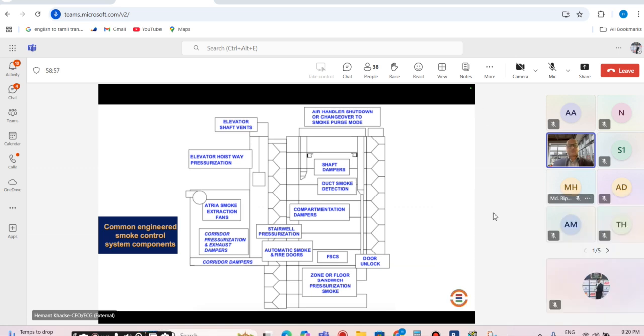personally, I am always in favor of not pressurizing the lift well when your lobby and staircase are pressurized, and that becomes your fire shaft or protected shaft for first responders. But when integration is possible, it is important that your differential pressure is maintained. If you don't maintain your differential pressure, what has been regulated, then the purpose is defeated.